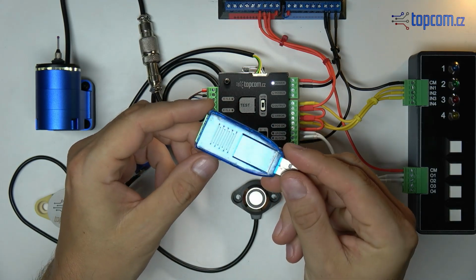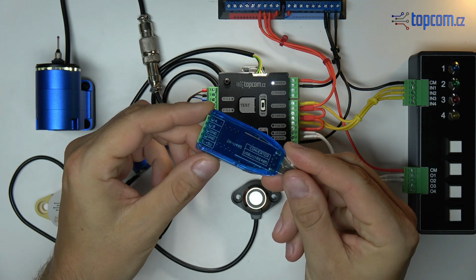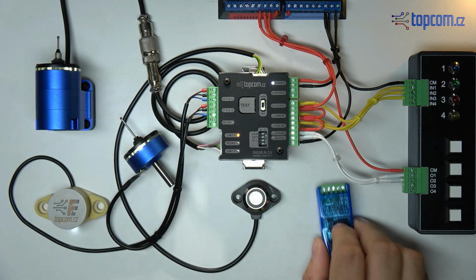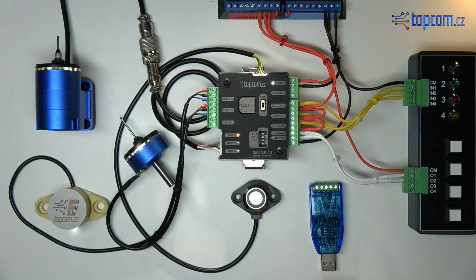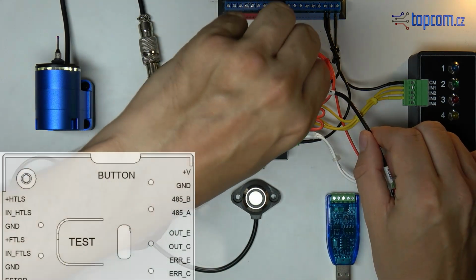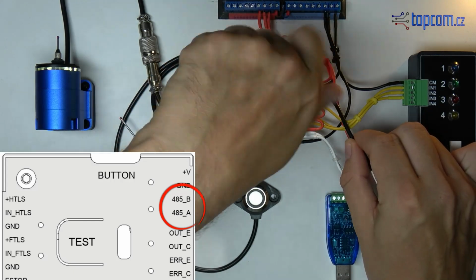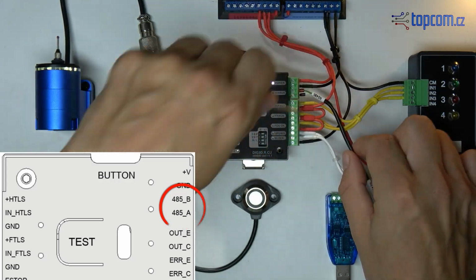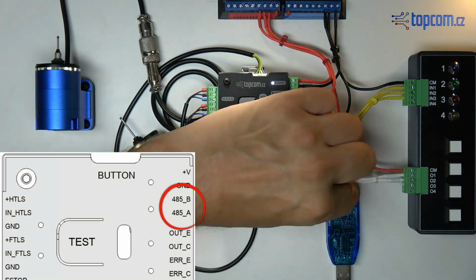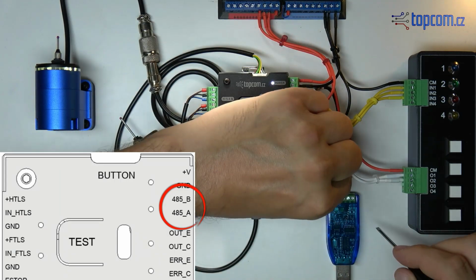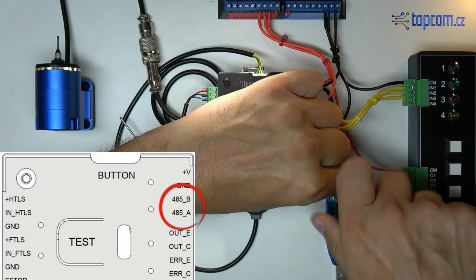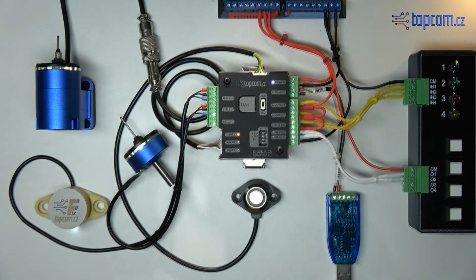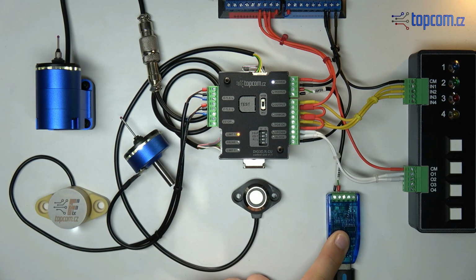To connect it to your computer, you can use the USB converter included in the set. However, any other converter that provides an RS-485 interface can be used as well. The wiring is very straightforward. Both the control unit and the RS-485 converter have terminals labeled A and B. Simply connect the corresponding terminals between the control unit and the converter. Finally, connect the converter to your computer. With that, the wiring is complete.